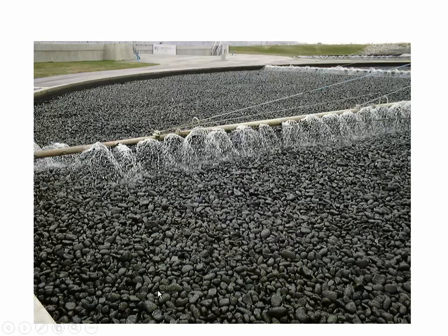Here's a picture that's showing sort of an isometric view of it here. So here's an arm that's rotating around, and sometimes they'll put a motor on the center just in case the water flow rate's not enough to power it. But you'd have rocks here that have a thin layer of bacteria living on the surface of the rocks. So when the water is sprayed, the bacteria are reaching into that water and taking out their food.